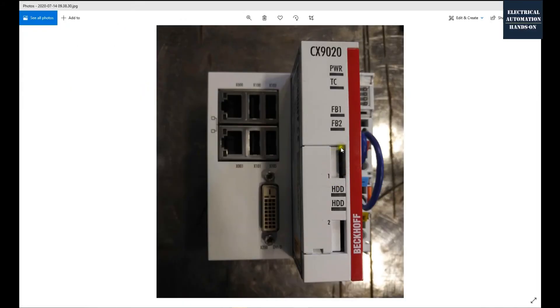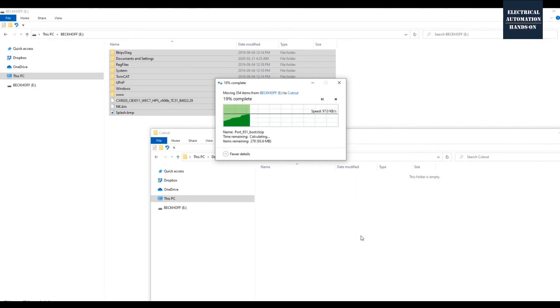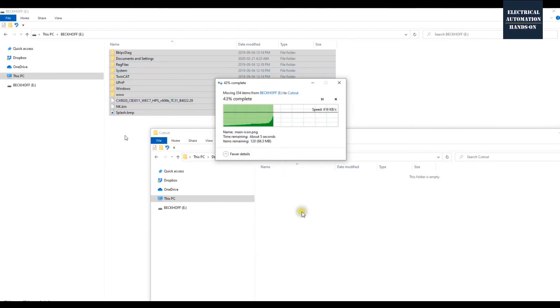Download the zip file for the new firmware. Then, with the system shut down, remove the CF card or micro SD card from the controller. For the CX9020, it uses a micro SD card. Remove this card, plug it into your laptop, and copy all the files from the micro SD to your local hard drive. You will see the files are named with version 4022, which is the current hardware version on the CX9020.